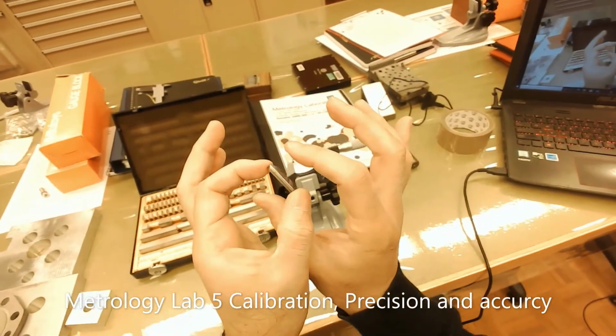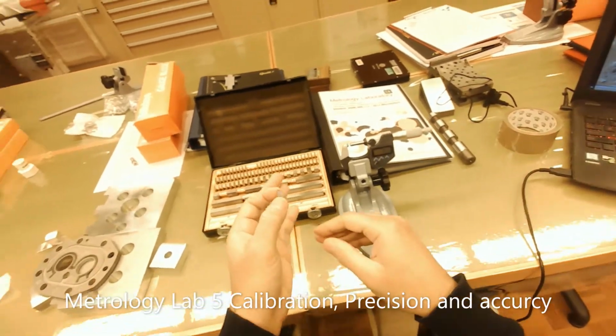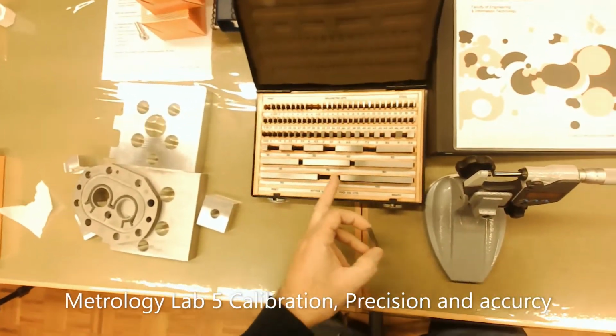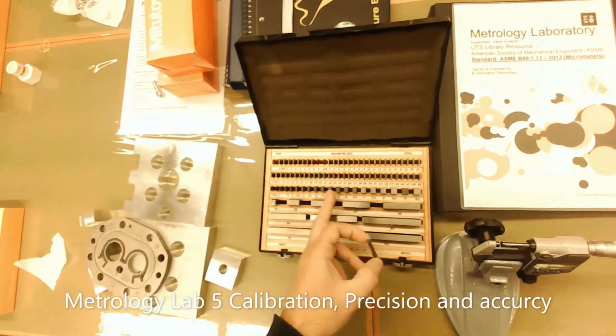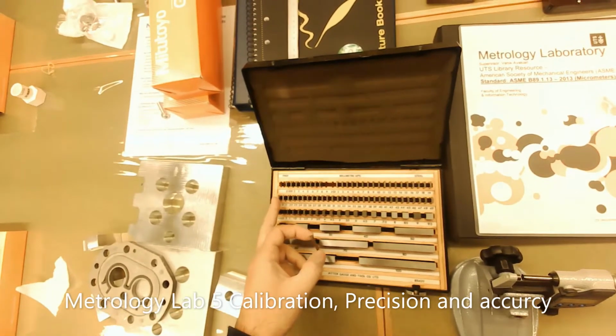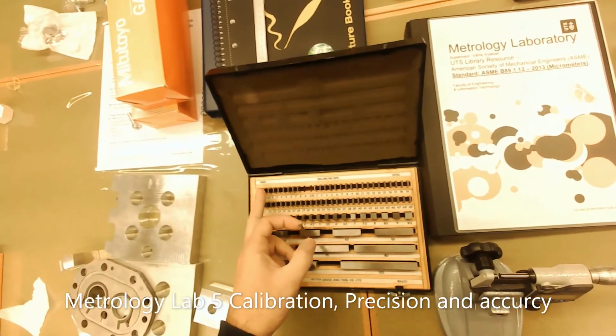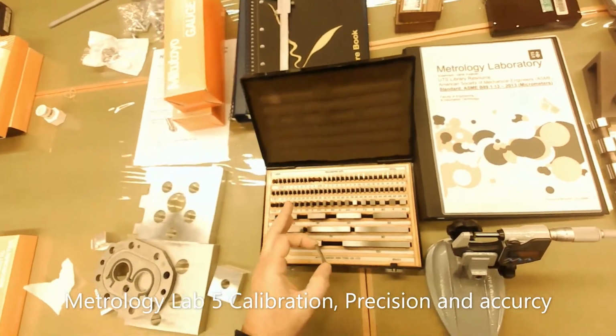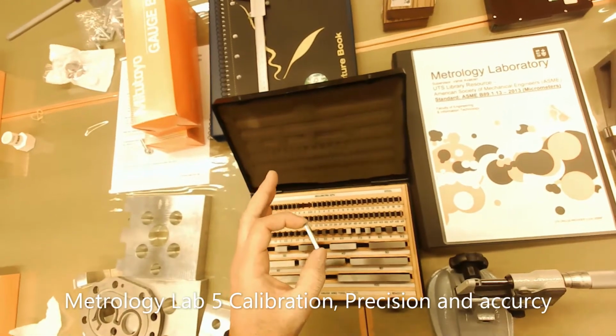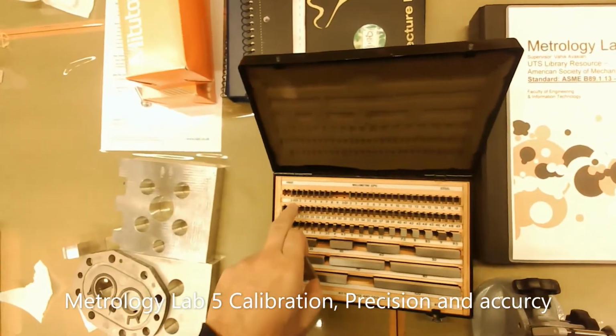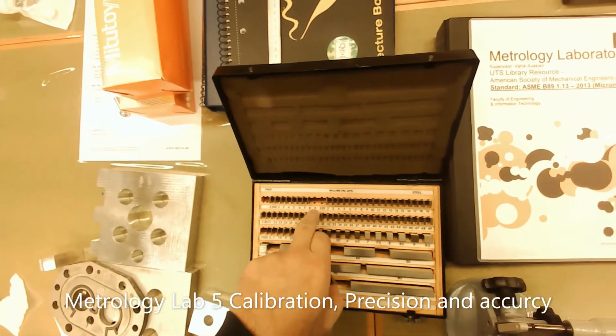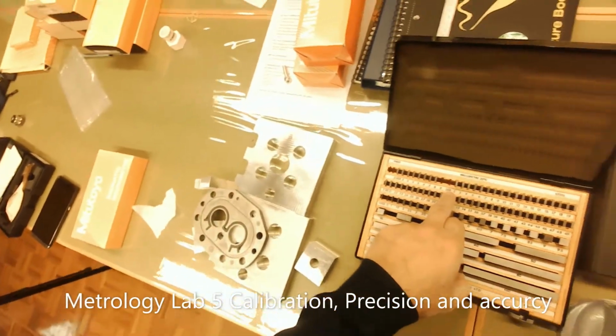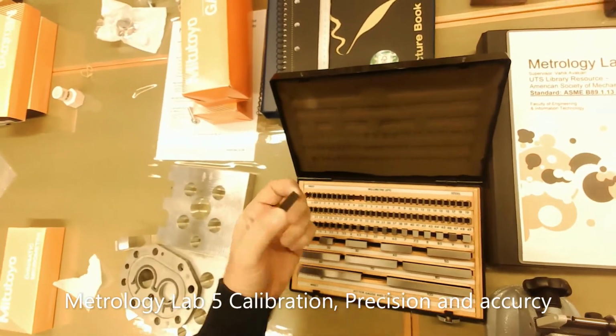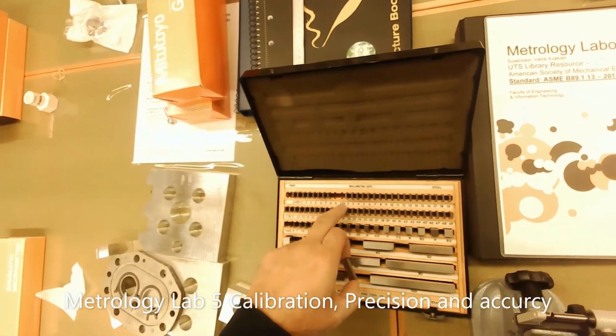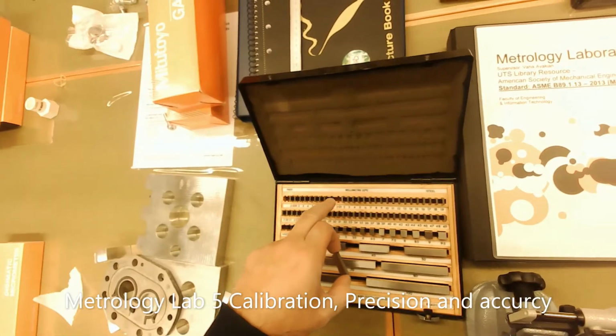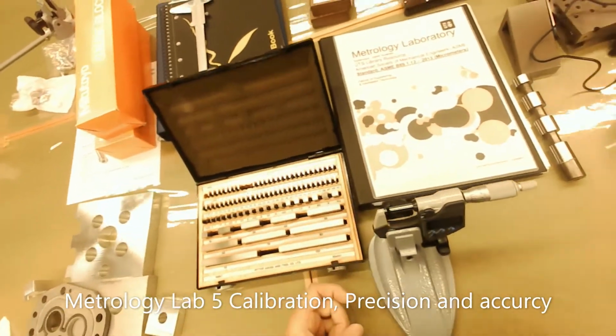Now, we build up a certain thickness by using these gauge blocks, which change in steps of tens, half millimeters, hundredths of a millimeter, and thousandths of a millimeter. We can build up any value and use it to check the accuracy of our measurement. What I chose here was 2.009 plus 2.01. Adding these two values, 2.009 plus 2.01, gives 4.019 as the reading I'm supposed to get from my micrometer.